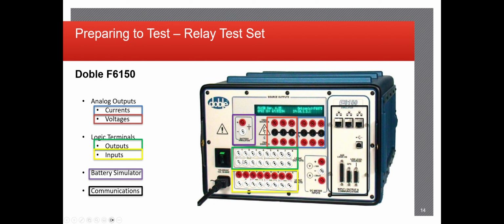Your logic outputs are here in the green. Those are what you'll be hooking up to all your relay inputs, because from the test set you're going to be operating something that the relay may want to see, sending DC voltage up into the relay input and then back out to the receiving end of the logic output at the test set. Logic inputs, pretty much the same but reversed. You're going to hook these up to the outputs of the relay to make sure that the test set sees when the relay operates an output and make sure that it's the correct one.